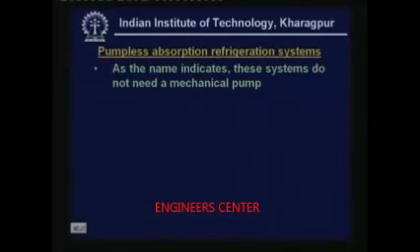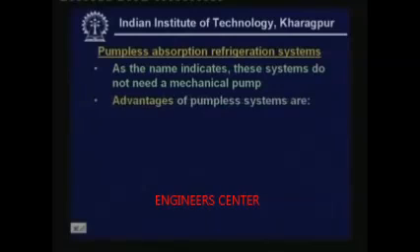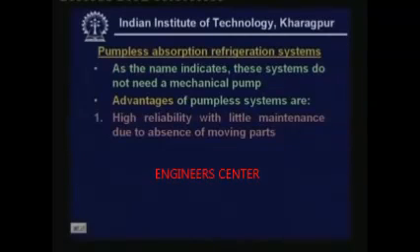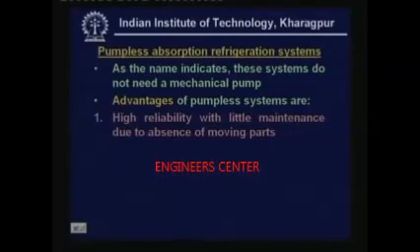Let us look at some of these pumpless systems and their features. These systems do not need a mechanical pump. The advantages are high reliability with little maintenance due to the absence of moving parts. In a pumpless refrigerant system, you do not have any moving component at all. Once you do not have any moving component, reliability will be extremely high because, frankly speaking, there is nothing that can go wrong. No maintenance or servicing is required - this is one major advantage of pumpless systems.